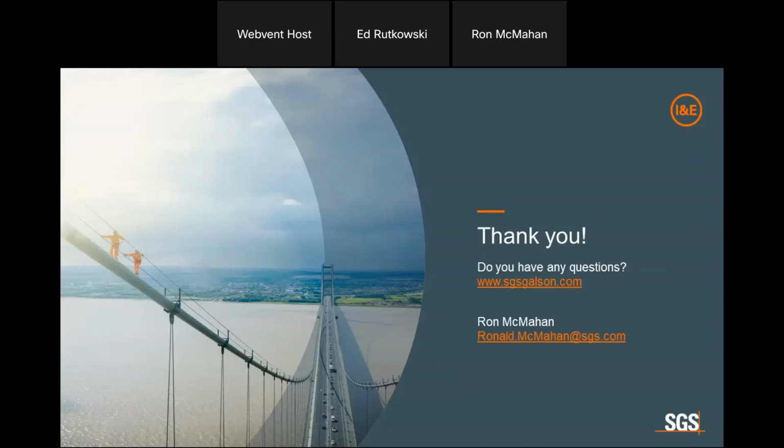Part of the issue that we ran into was the speed that we were installing and the ability to verify calibration and do any modification upon installation. That's the reason for the first year, we're actually going back and looking at that data, and trying to determine if we can do a back calculation to see the data correction or how bad was the data. And we're in the middle of that right now.